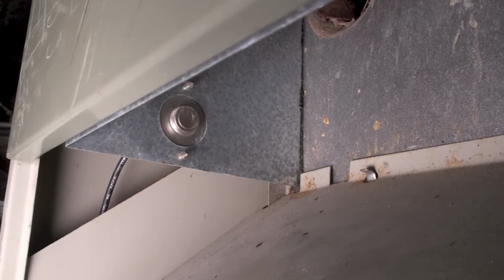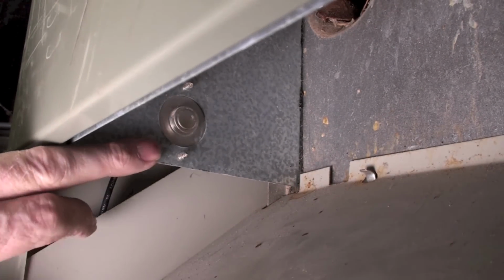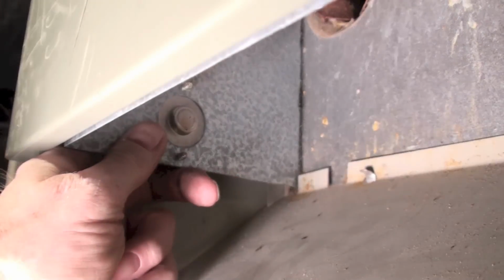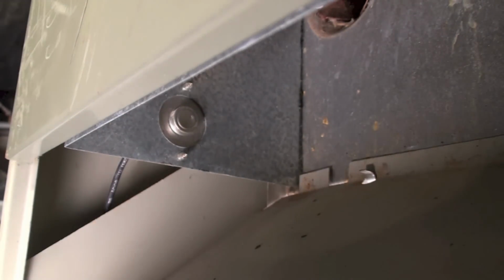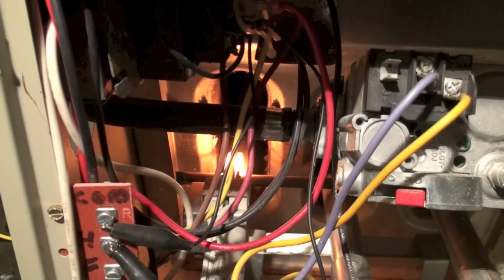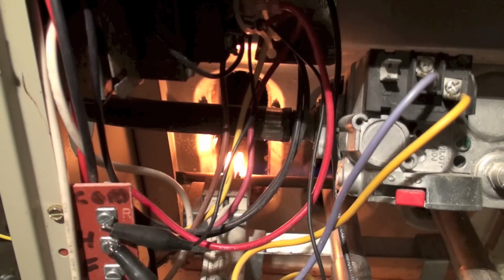Now, here we have a close-up of the draft hood. And right here is this little switch. Now, I've got it kicked off. You can reach around behind the silly thing, and there's a button on it. You heard that little click. Well, let's look down here and see what's happening. Hot surface igniter's warmed up. Let's see what happens now. Okay, it's hard to see that flame down there. You see a little blue flame? There we go, and the burner came on. So in this case, what had happened is you'd had draft spilling out of this draft hood, and it shut it off. So you need to find out if there's any problems in your venting or something like that.